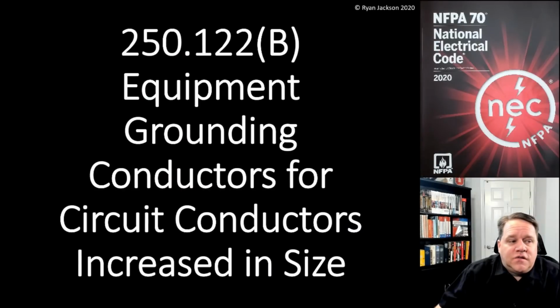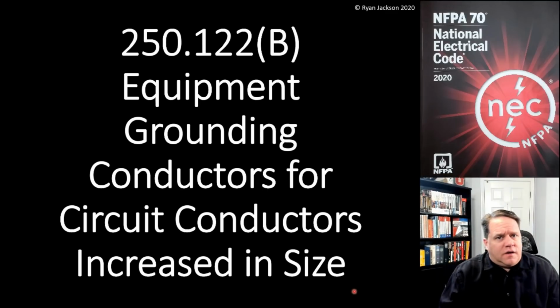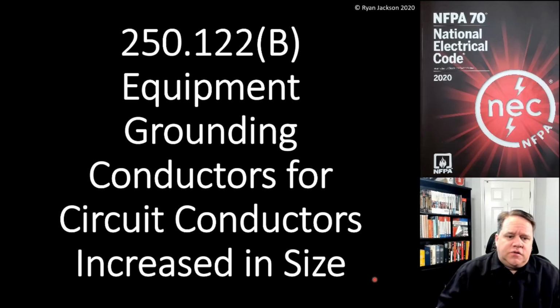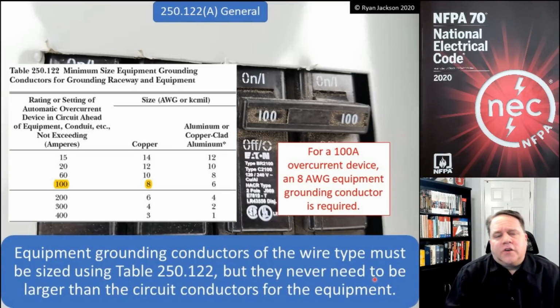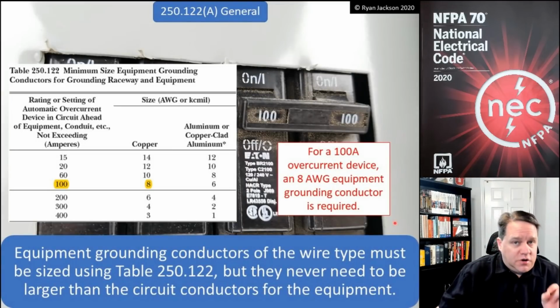This is kind of a difficult subject because for some applications, it makes perfect sense. For other applications, it makes no sense whatsoever. So let's go ahead and take a dive into it and see what 250.122(B) has to say. Now, before we get into B, we kind of have to cover A first, because 250.122(A) talks about how to size the equipment grounding conductor in general.